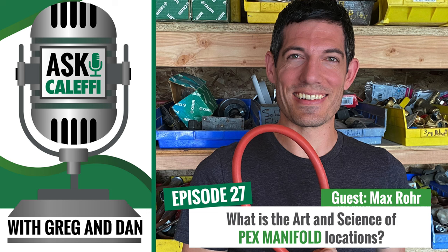Max, what's the benefit of using PEXL PEX over standard PEX? One thing my dad liked about PEXL PEX when he was doing systems is that it has more memory. Especially near boiler piping, you can make that look really nice, and even use the copper bender to make sweeps instead of using fittings. It's a lot easier to wrestle with because it will stay in shape, compared to the A, B, and C PEX that want to come back to wherever they've been sitting for a long time. Or with a heat gun, you can get an A to straighten out a little bit, but this is easier to wrangle. I've also seen that standard A, B, or C PEX starts to move and change shape as it heats up, where PEXL PEX holds better. Yeah, that linear expansion. It doesn't move around as much with that metallic layer sandwiched between the two polymer layers.